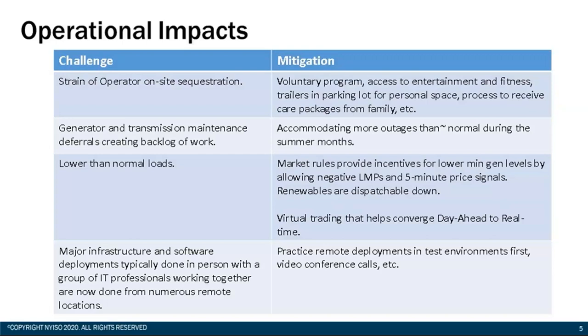One point about low loads and voltage we didn't really see: this hit us pretty hard during the typically low load spring season. There were definitely lower loads during the day, but our lowest loads, where we normally see voltage issues, are in the overnight hours, and those didn't experience as much demand degradation as we'd normally expect. So any voltage issues we experienced were our typical low load, shoulder month, overnight voltage issues, nothing out of the ordinary.